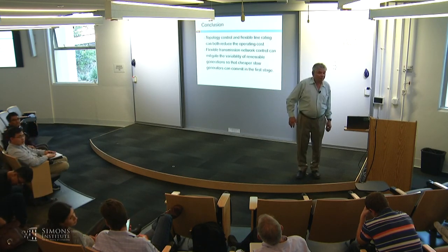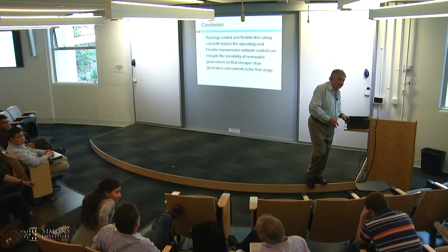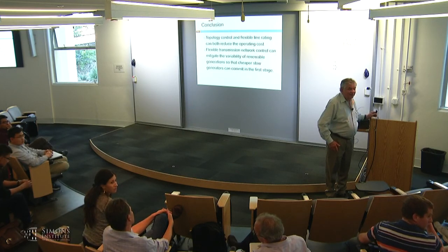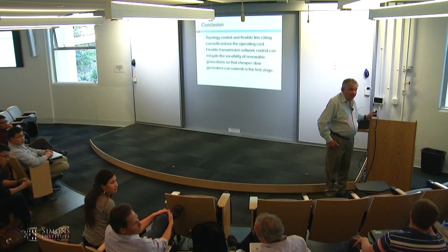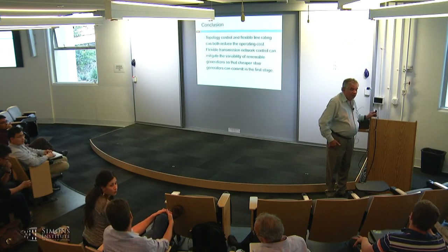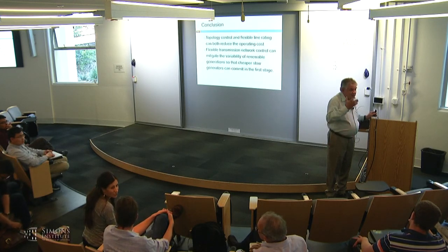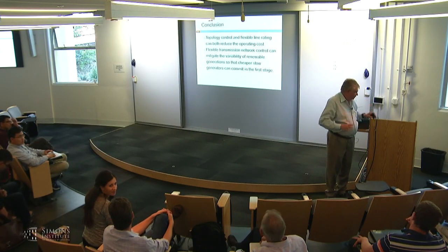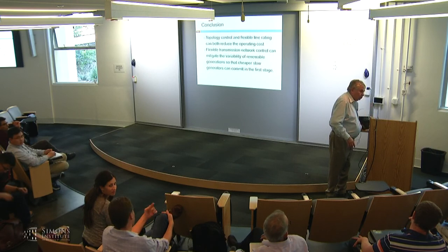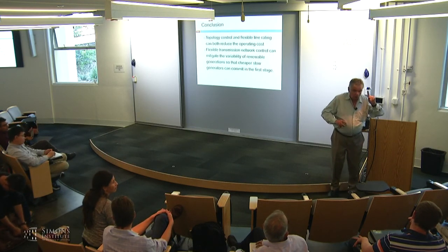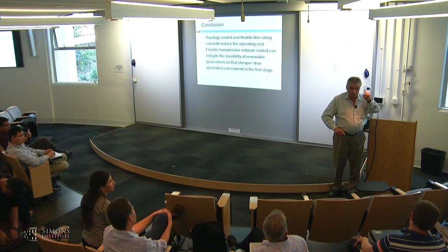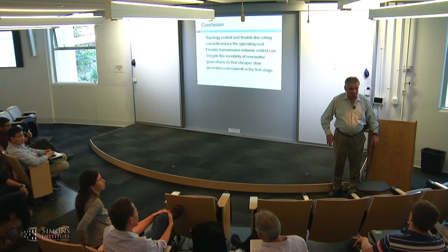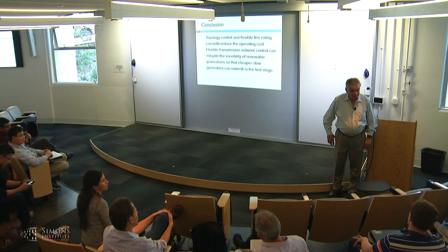How to tackle the combinatorial complexity? So pick 5 lines out of 1,000 lines, like 1,000 to the power of 5. They are quite tremendous. How do you tackle that? Well, as I said, at PJM we're kind of aiming at this. When we did the topology control project, we said at any point you can switch 1 line per day. Which would be the best line to switch? And just this capability saved $100 million in the simulation.